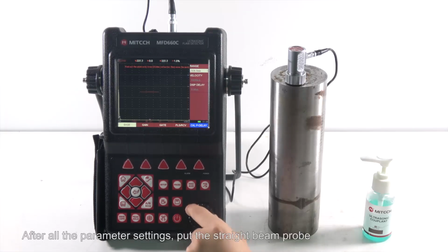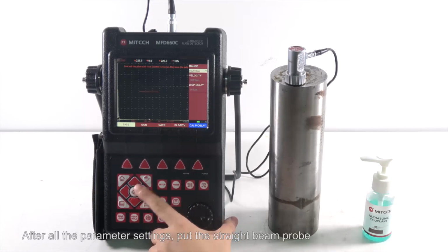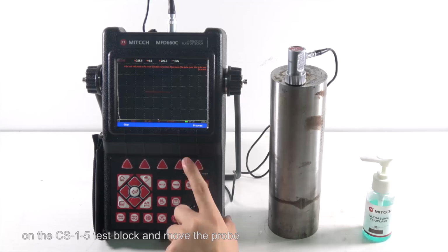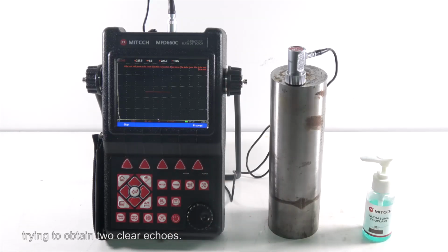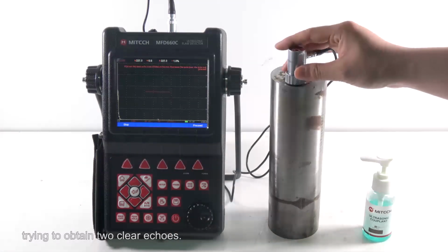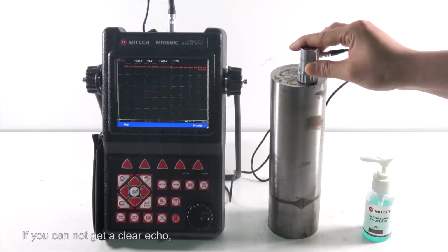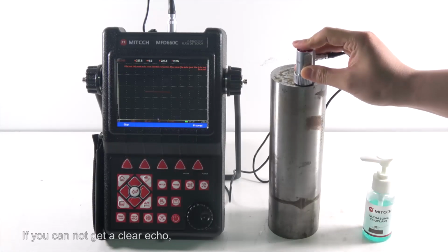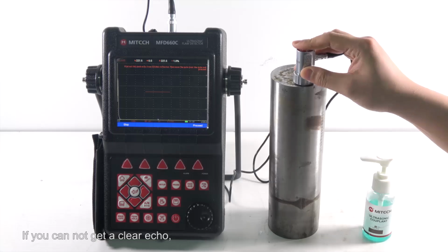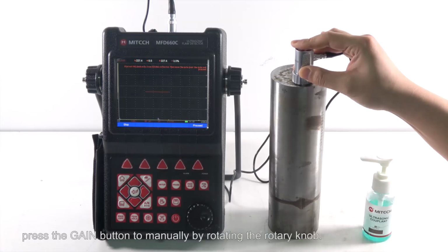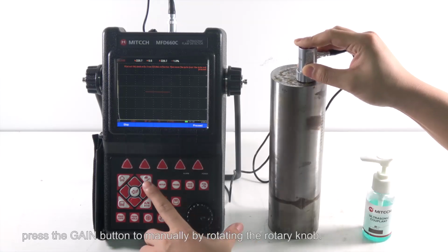After all the parameter settings, put the straight beam probe on CS15 test block and move the probe trying to obtain 2 clear echoes. If you can't get a clear echo, press the gain button and adjust manually by rotating the knob.